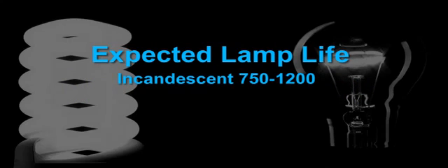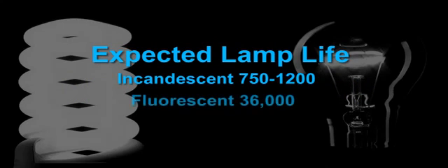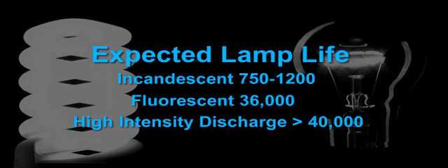The standard incandescent has a life expectancy of about 750 to 1200 hours. Fluorescent lamps are rated up to 36,000 hours. Nevertheless, some high-intensity discharge lamps are rated for up to 40,000 hours, while LED technology has increased the operating hours to as much as 80,000.